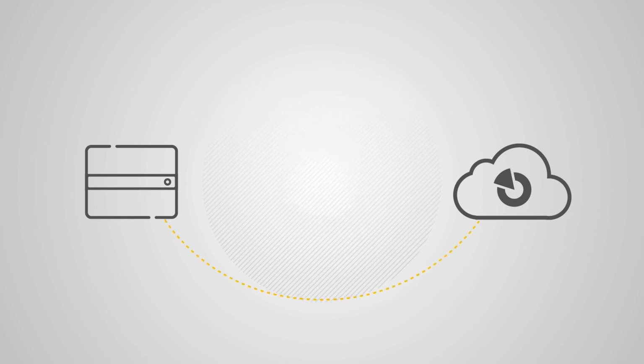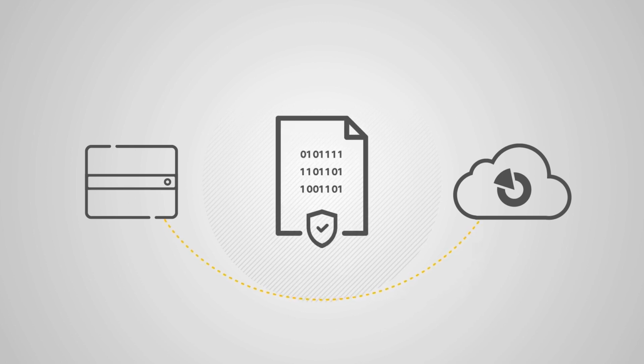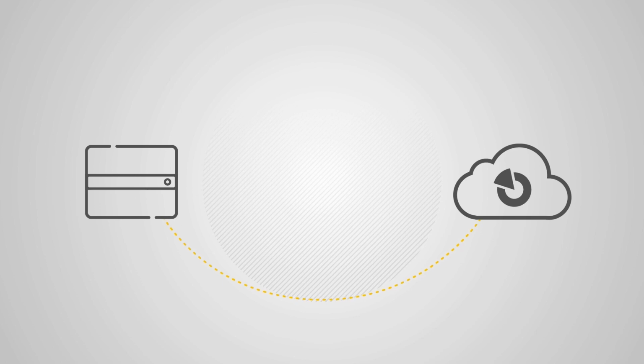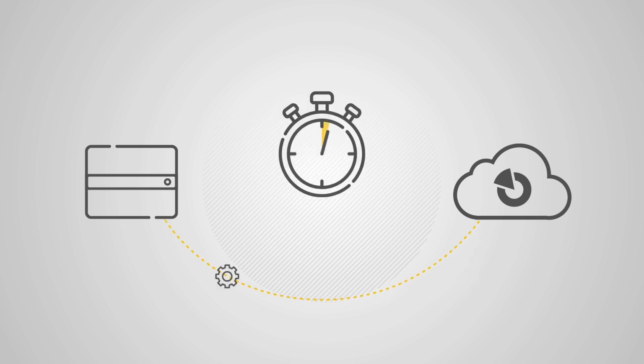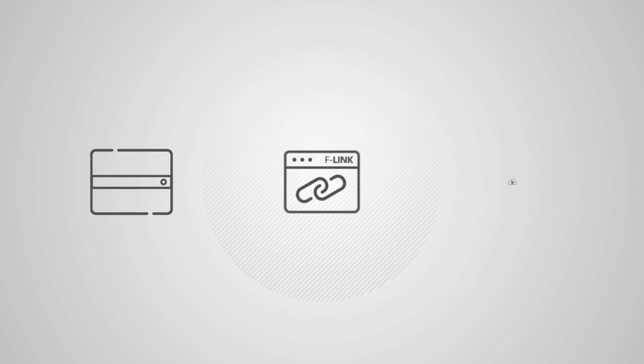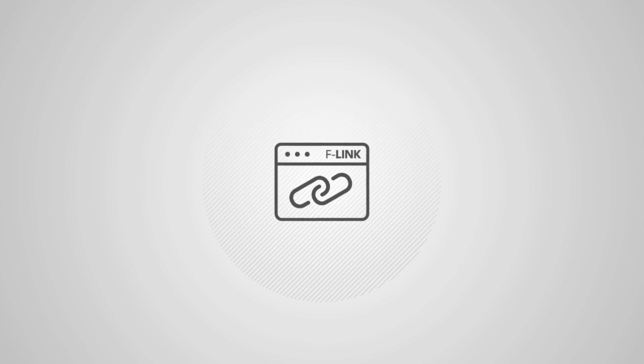Channel 2 acts as a controlling channel. It provides only data communication with no backup. It is used for controlling the system, and it sends the status of the system when changed. Change of temperature, signal strength. Communication runs on Jablotron proprietary protocol and is secured by a persistent connection with only a 15-second heartbeat without confirmation. Delivery of the information is not confirmed. Communication is to be set in F-Link software, the Communication tab in the Jablotron Communication menu.